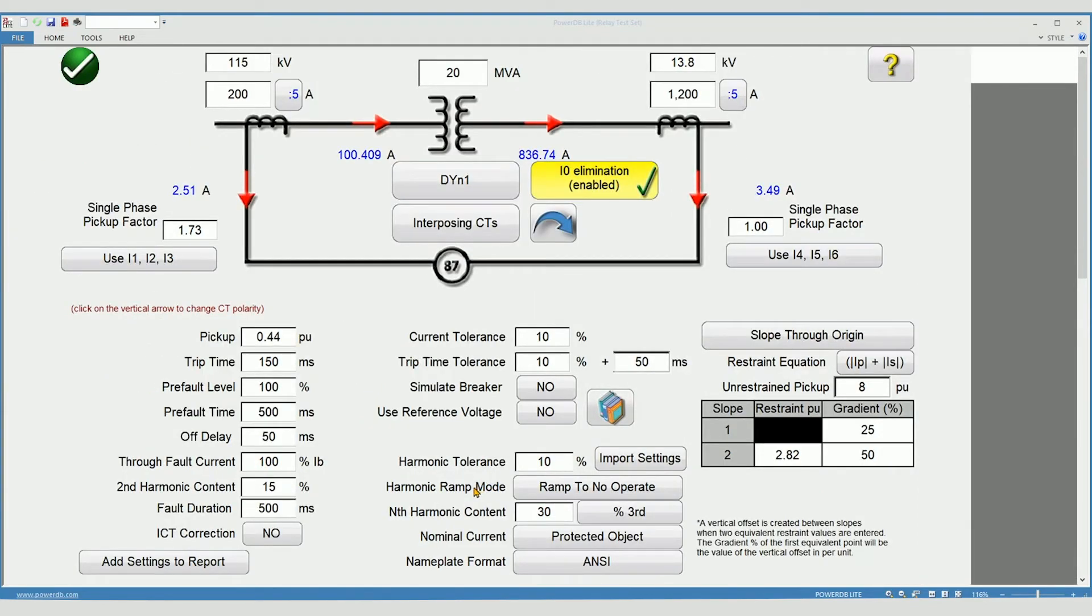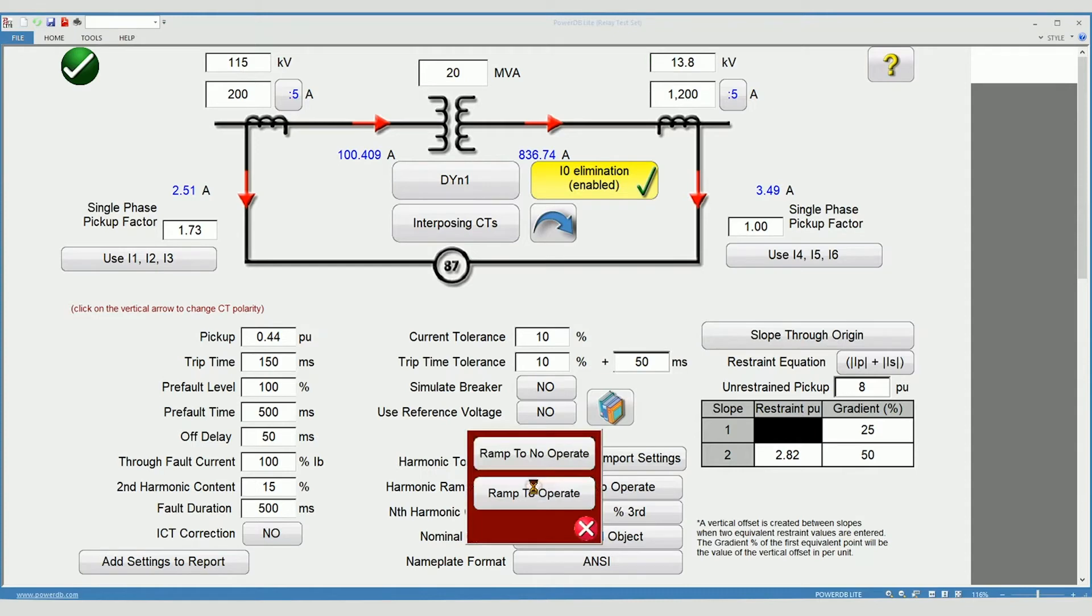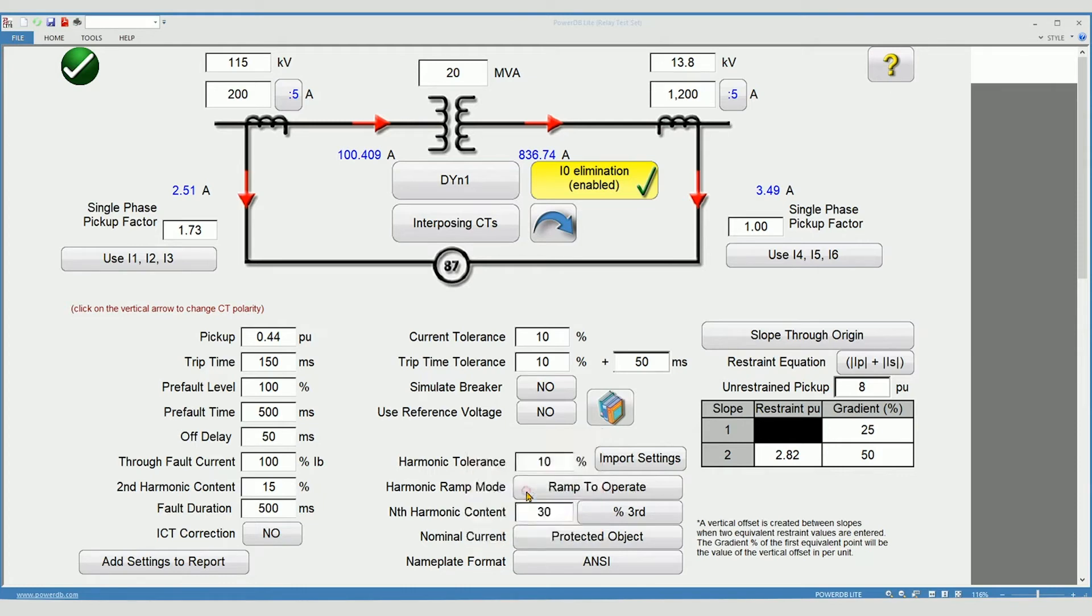Harmonic ramp mode. This allows you to choose to ramp from an operate to a no operate condition or from a no operate to an operate condition. Fault duration. During the test, short fault pulses will be applied to the relay. This determines how long the fault pulse is.